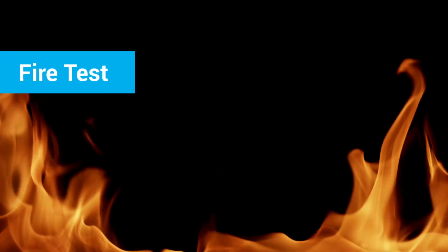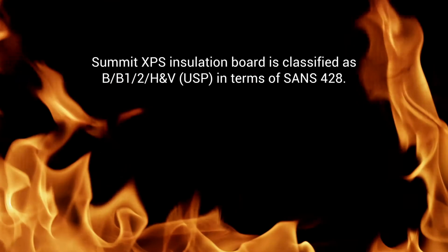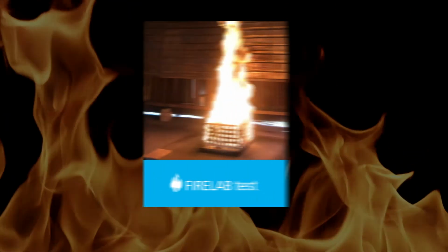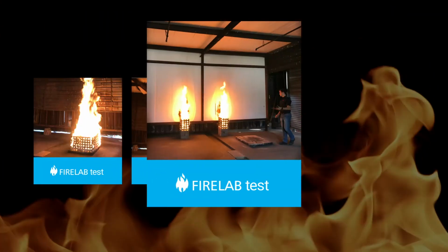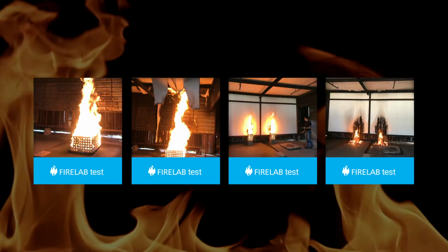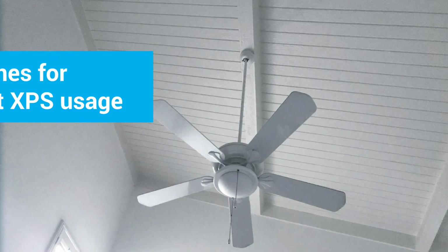Although it's combustible, it poses no flame spread hazard. It can be installed horizontally or vertically in most buildings, with the exception of regulated buildings that specifically require non-combustible materials. When exposed to fire, XPS board softens and shrinks away from the heat. It produces no flaming droplets and will not spread flames.